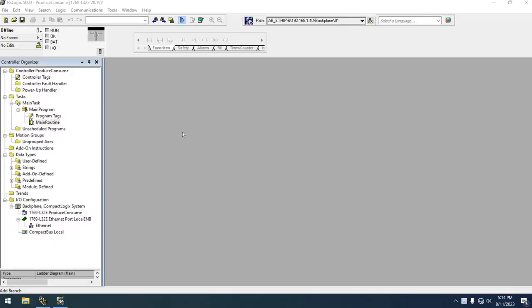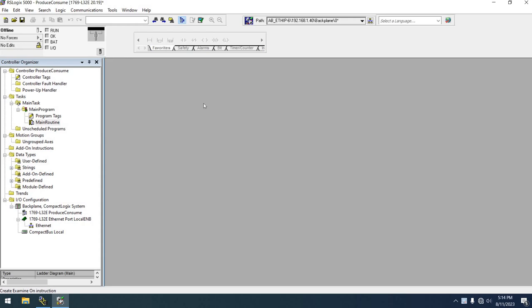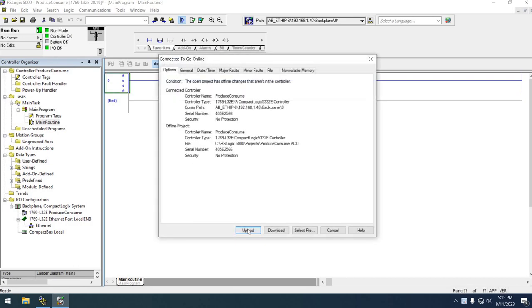Okay, guys, so I hooked this computer back up to our intranet, and I closed this software down, and I opened up my activation manager, made sure I could see my activation license server, and then I opened the project back up, and now you can see here, I can edit rungs. So I don't know, it was a one-time deal, maybe version 20 or maybe RSLogix 5000 had never opened.